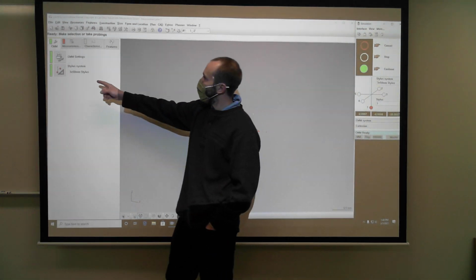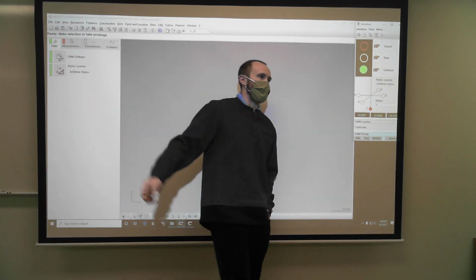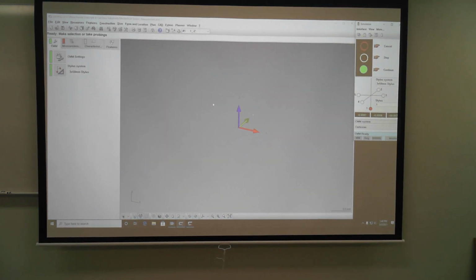All right, now you notice the stylus system that I have here. This stylus system is already green, meaning it's already calibrated. And you'll probably find that on all your machines, it's already calibrated as well. Do any of you have red on that screen? It's going to be on the CMM tab. Do any of you see red here? If you see red here, even when you have a stylus in position, it simply means that it has not been calibrated yet.